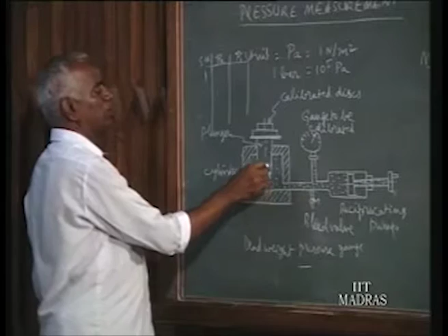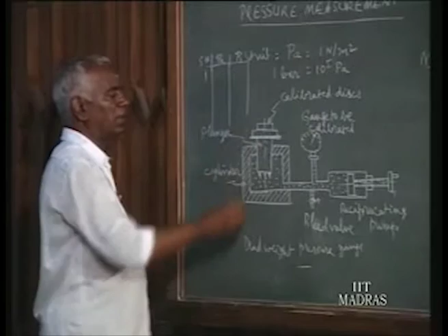Like that, whatever we have learnt under static calibration, we can develop different pressures here by adding more and more calibrated discs. Each disc has some pressure written on it. If 4 or 5 discs are added, add those pressures together. That is the total pressure developed, and whatever is indicated is written here, true pressure and indicated pressure in the instrument, and a set of readings can be taken. Again from the high pressure we can go back to the low pressure. That is the way we have learned static calibration. It can be done here.